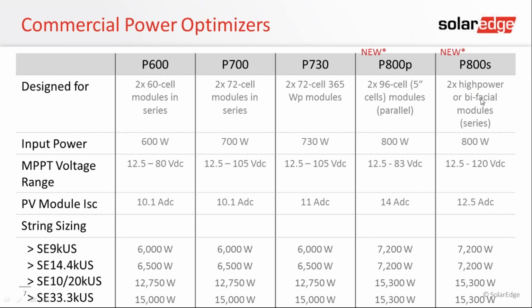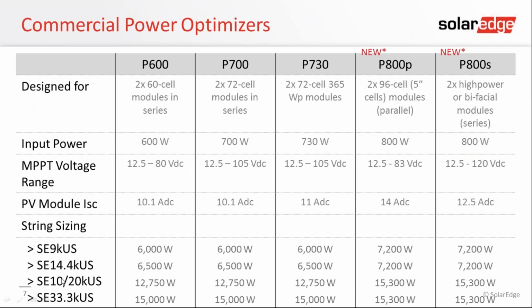The P800S is going to be your high power bifacial modules, or just your high power 2 modules in series, and that's what the S stands for, series. For the 600 and 730, these basically, again, are 2 modules in series to 1 optimizer. Now, the important thing here is, let me go back, sorry. Look at the bottom row.